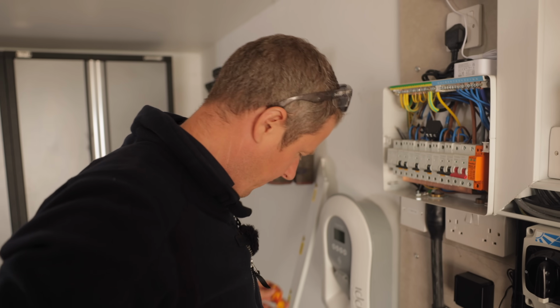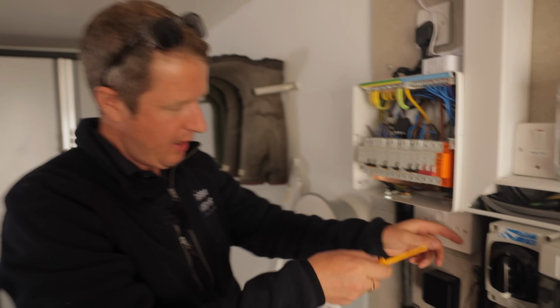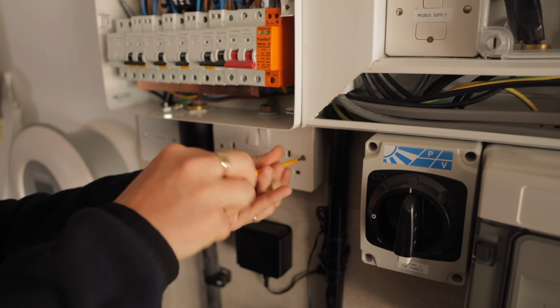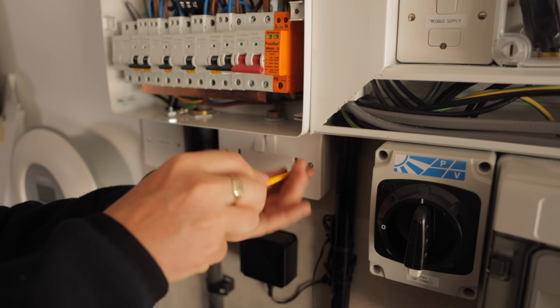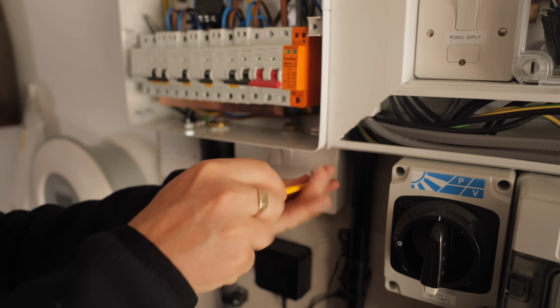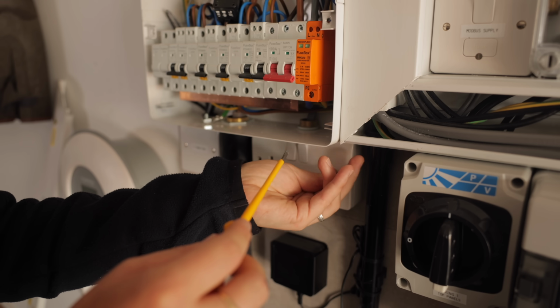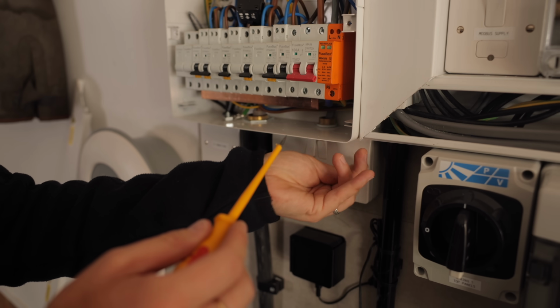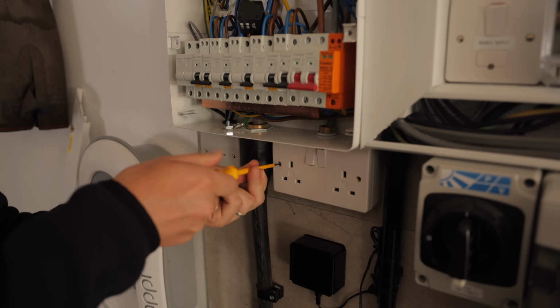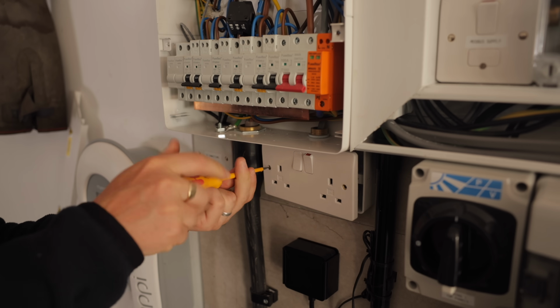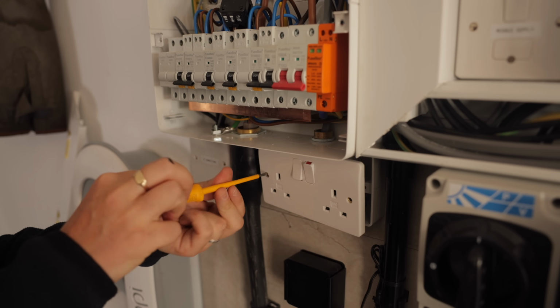So for running the power to our Libbi controller, we're going to run it off this socket circuit that we've already run in. There's only 1 cable going into that at the moment, and it's just on a 16-amp MCB. So we might as well just do that, and then it'll be easy to run the cable over to our switch fuse connection unit for our Libbi controller.